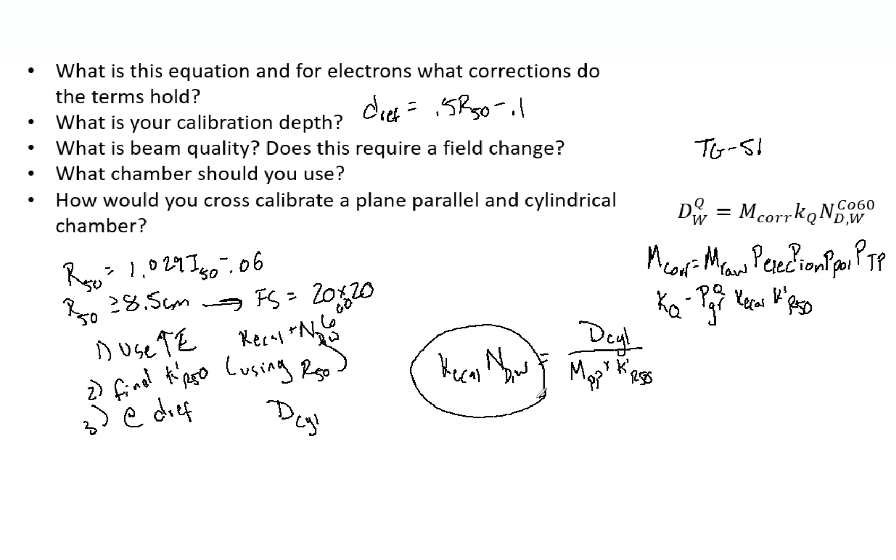We need this factor to do TG-51 with the plane parallel chamber. We're going to find the dose with the cylindrical chamber, then the reading with the plane parallel. And then remember, we found K-prime R-50 using the R-50 and some tables and things within TG-51. You know all three of these values, you find that, and then you were able to do TG-51.